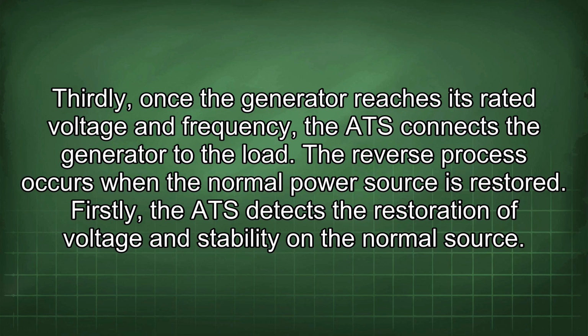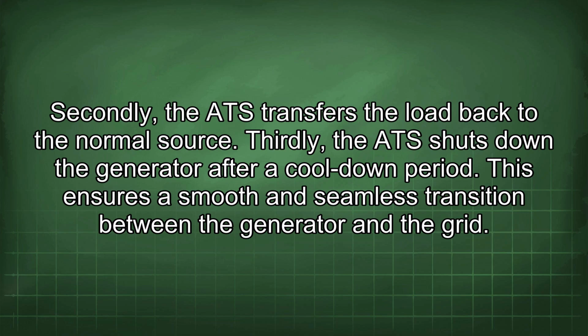The reverse process occurs when the normal power source is restored. Firstly, the ATS detects the restoration of voltage and stability on the normal source. Secondly, the ATS transfers the load back to the normal source. Thirdly, the ATS shuts down the generator after a cool-down period. This ensures a smooth and seamless transition between the generator and the grid.